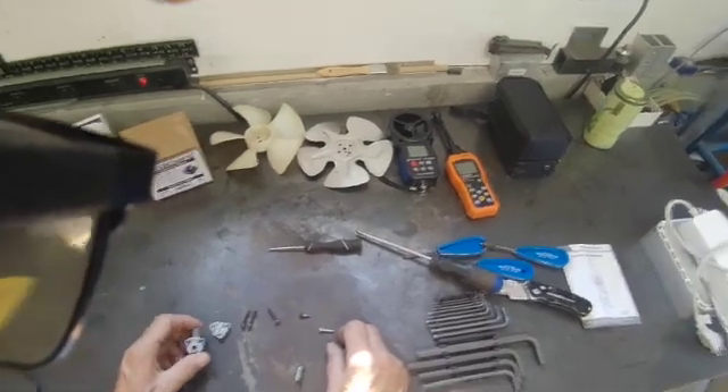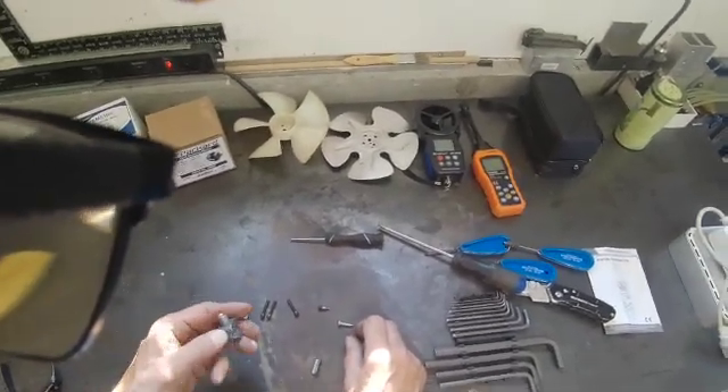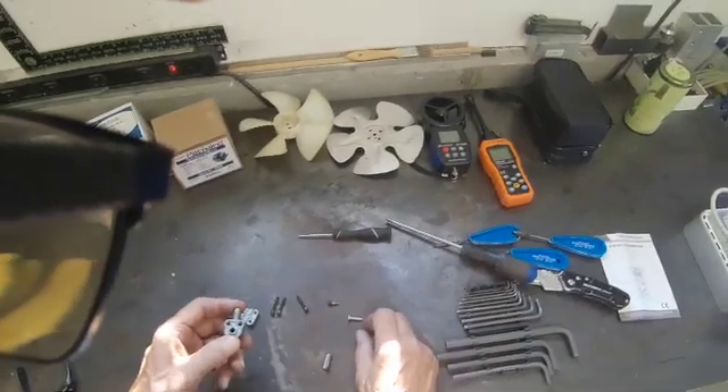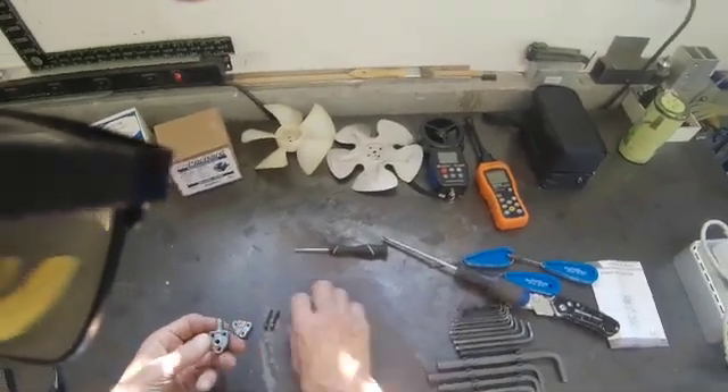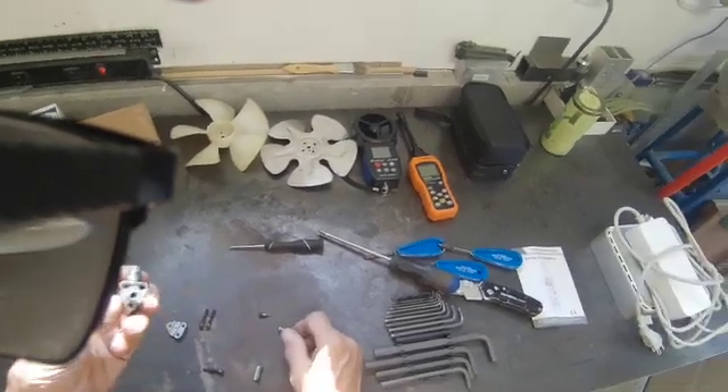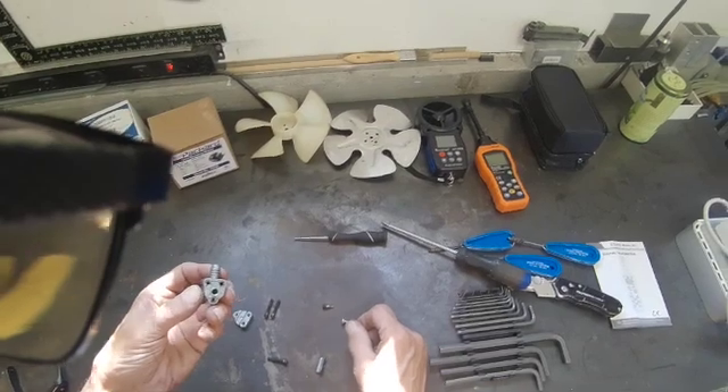I went on another job yesterday and had the same problem — put one of these Supco line tap valves on and got a zero reading. Out of curiosity, I loosened the screws on the tap valve and then I could hear gas coming out.